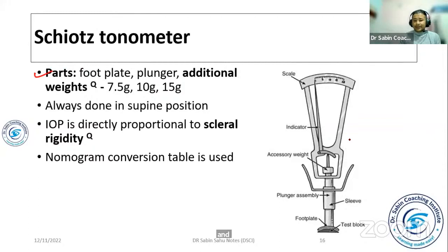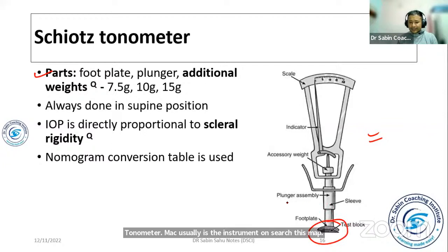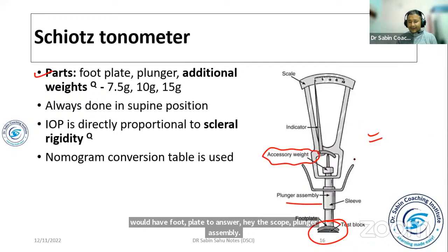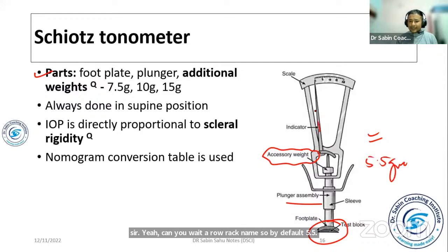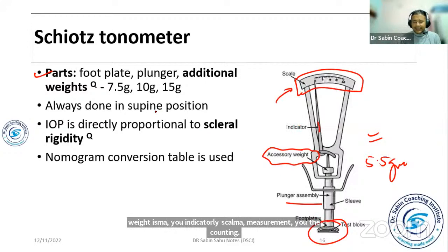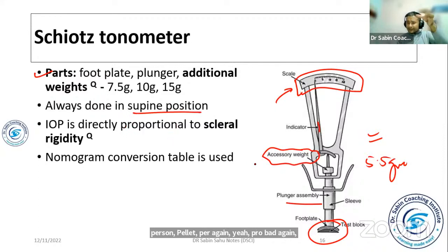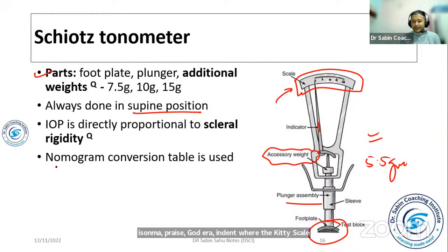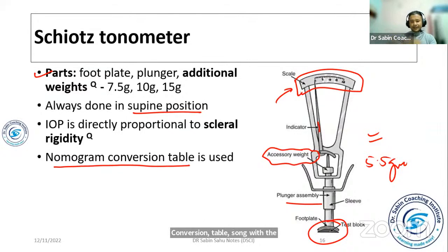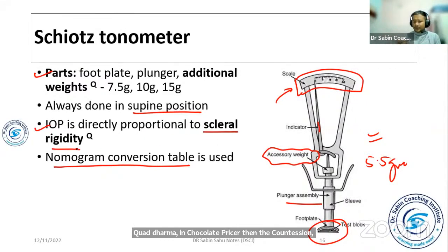In the Schiotz tonometer, the instrument has a foot plate. By default, the weight is set to 5.5 grams. There is an indicator on a scale for measurement. The foot plate is used to indent or applanate the cornea, requiring topical local anesthesia. The IOP measurement depends on scleral rigidity to ensure reliability.